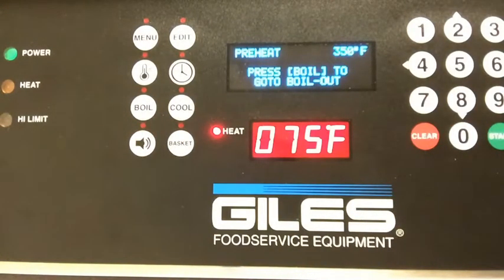Sometimes during the morning when you try to fire the unit up, if you have extremely cold oil, the oil will heat in a certain area and get above that temperature, and it'll give you error messages like that every once in a while. But by just stirring the oil and pressing the start button, it'll clear it and you'll be able to get beyond it. That is a safety, just like having the drain valve switch to keep them from firing the unit up if the oil gets too low.